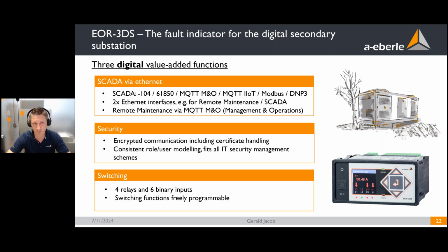For example, the protocols supported include IEC 60870-5-104, 61850 Goose, Modbus via TCP, DNP3 via Ethernet, and the two latest protocols we implemented based on MQTT. One is IoT, to get all the data into a big cloud, or most likely on-premise at the DSO, to have this big data possibility. The second protocol is for management and operations, for remote maintenance of the device. We will see that later on in detail.